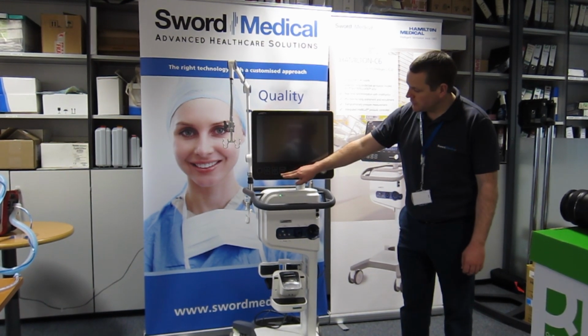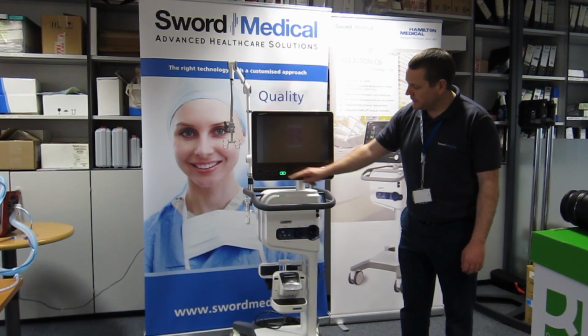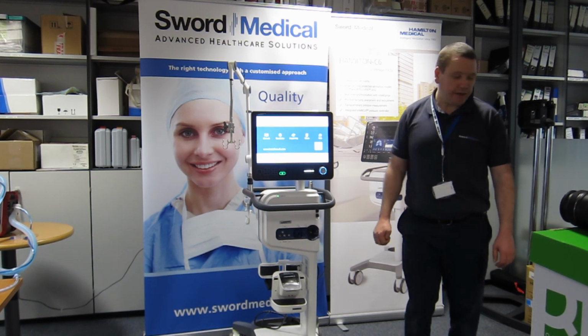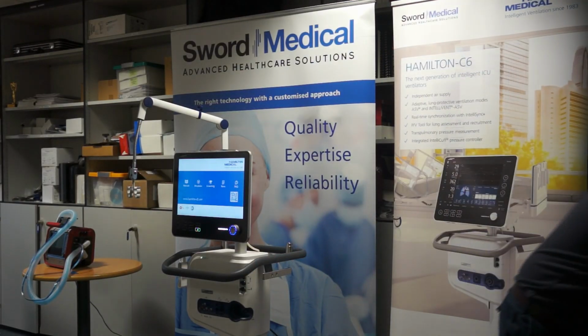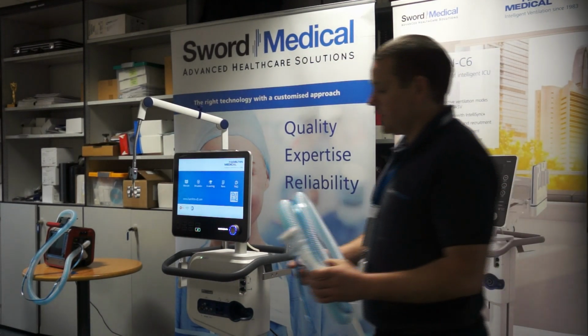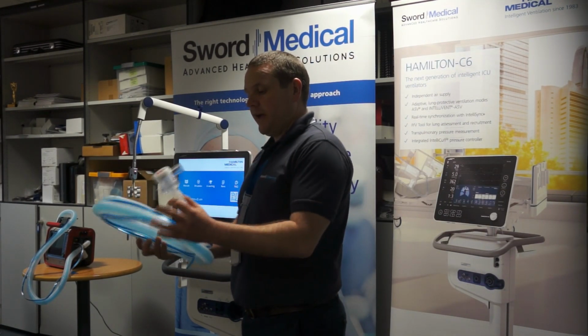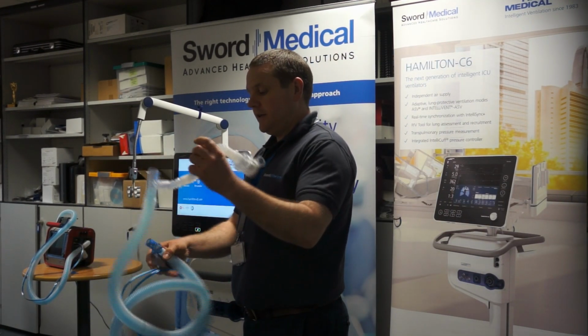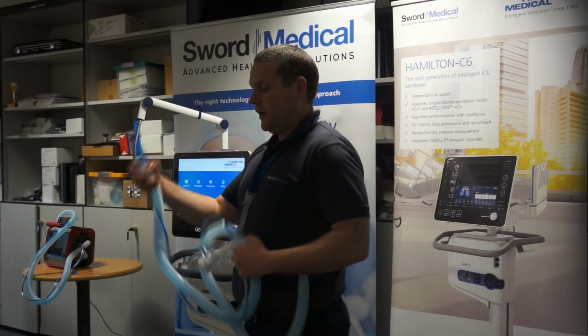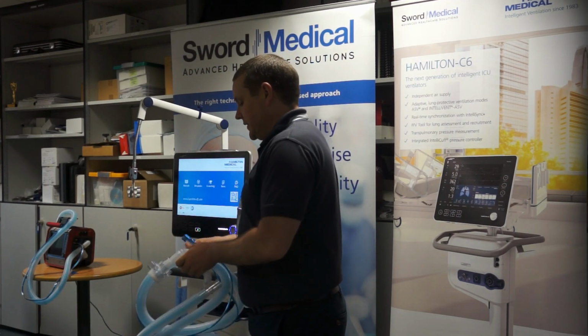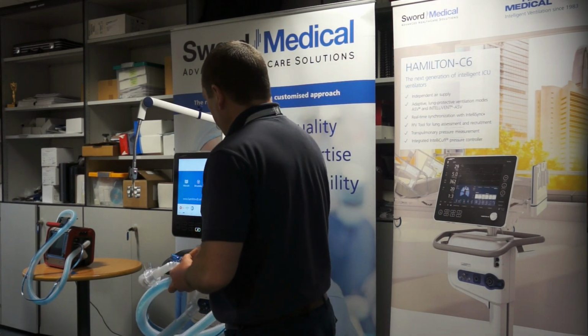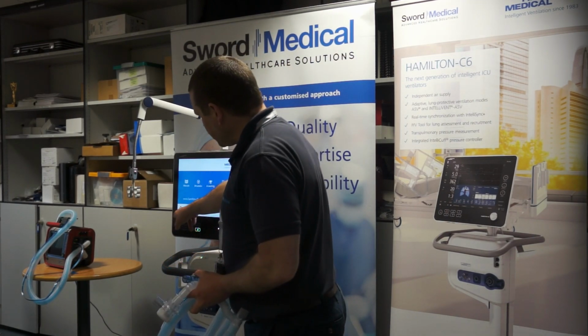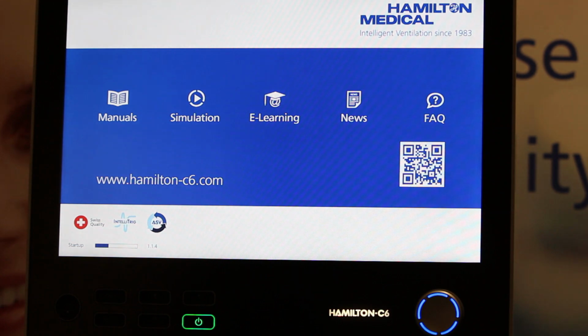So I'm going to start off by turning the ventilator on, and then I'm going to put a circuit on and show you how that goes in. So here is our circuit. It's got our expiratory valve on this end, and then our flow sensor on this end, the patient end. So I'm going to show you how that plugs on now. As I start up the ventilator, you'll see on startup it does its own self-test.